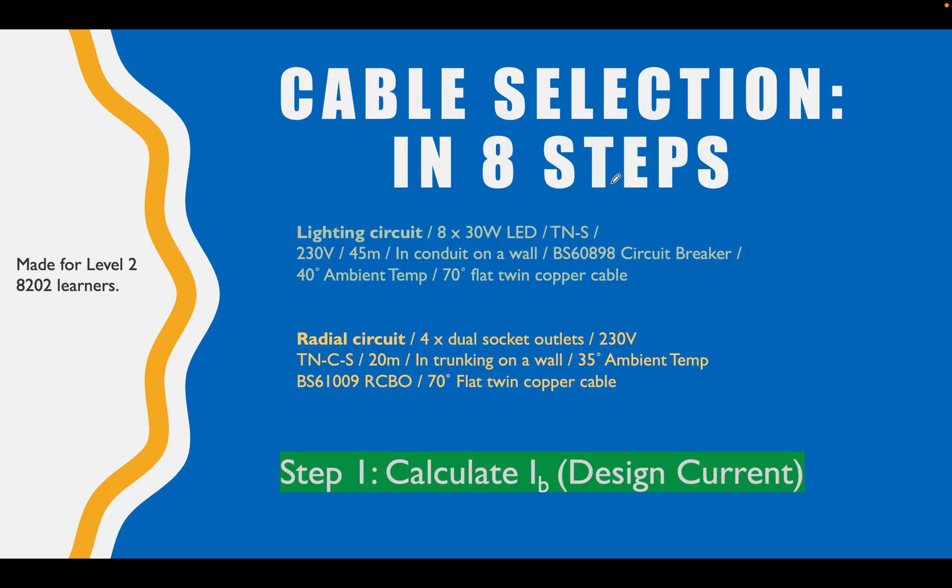Let's look at the screen for step one. These are the two circuits we're going to take through this process: a lighting circuit and a radial circuit. The lighting circuit is feeding 8x30 watt LEDs, and a radial circuit which is feeding four dual socket outlets. Let's have a quick look at these breakdowns - we're going to carry this information through and add to it as we go. The lighting circuit has 8x30W LEDs, TN-S system, 230 volt single phase installation. We've got the length, installation method, circuit breaker, ambient temperature, type of cable, and the same for the radial circuit.